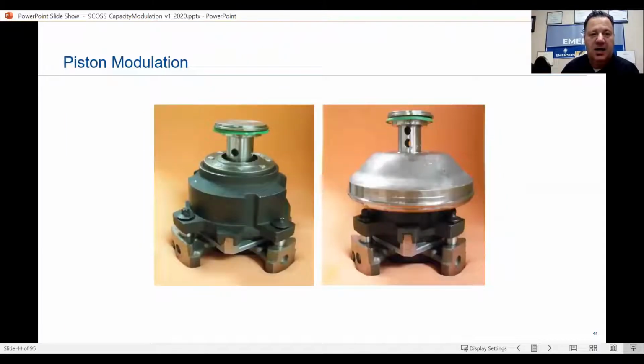Okay. Piston modulation, you can barely see it, but there's three little holes on this plunger right here, okay? And this is our floating seal. This is the fixed scroll bolted down with our Oldham coupling on top of our orbiting scroll, okay? And the way that is, it's a plunger. Again, it has male threads on the end of it. And when that scroll lifts up, basically the way this works is this is trickling out gas all along the way, and the major part of the gas, this is above that muffler plate that we talked about earlier that separates the high pressure from low pressure, and this is coming out of our plunger above that muffler plate.